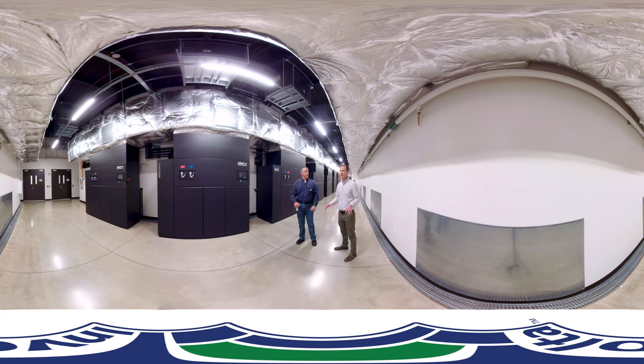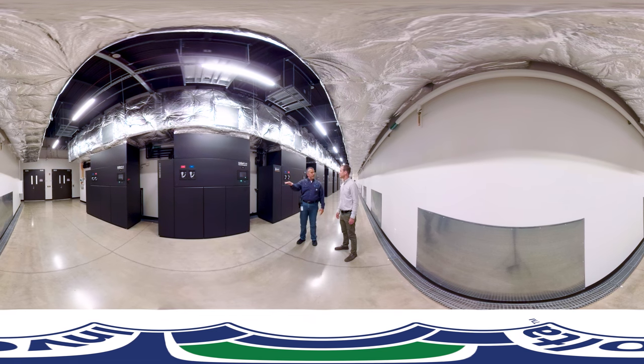Wow, so this room really is where the magic happens. It certainly is. In addition to that, we have a VESDA system that protects and monitors the airflow in those critical spaces at all times. We're looking at and monitoring the airflow going into and coming back out of that space continuously, because we're looking for anything that could denote a smoke signature in that airstream so that we can respond proactively and protect those critical assets for our customers.